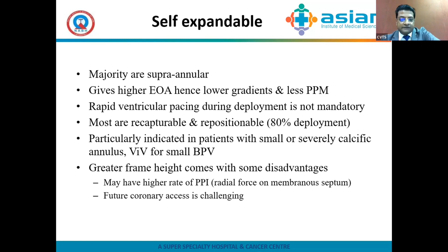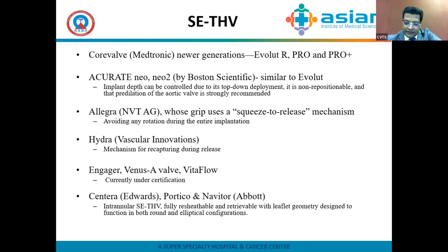Now, these valves are bigger profile. They have higher frame height, so that comes with a disadvantage. They may have high rate of PPI because they work on the radial force of expansion over time. And because of the big cage, which comes in front of the coronaries, future coronary access may be challenging as compared to the balloon expandable valve systems. The available systems are Medtronic's CoreValve, Accurate Neo, which comes from Boston Scientific, Allegra, Hydra, which is being developed by an Indian company, Engager, and Centera.